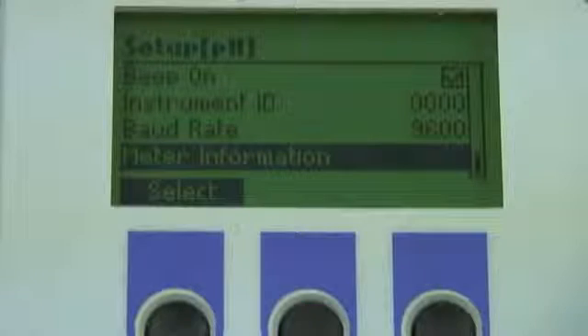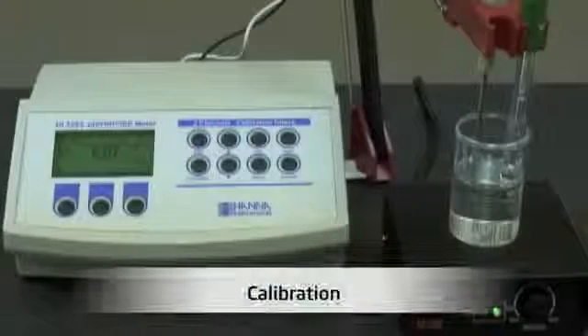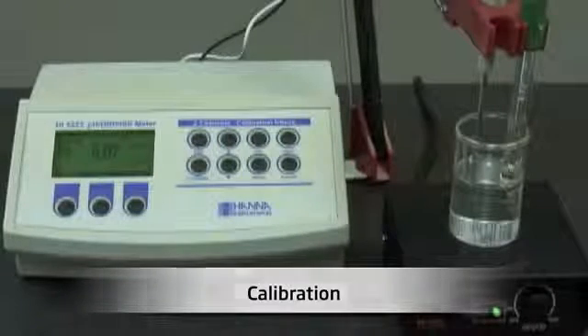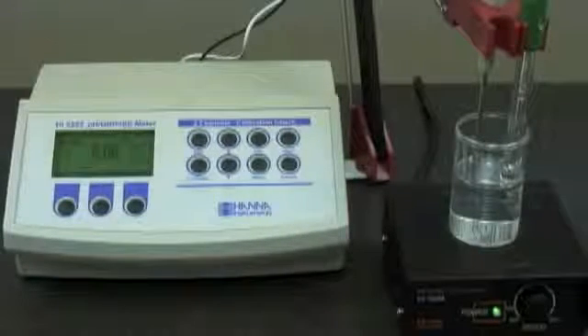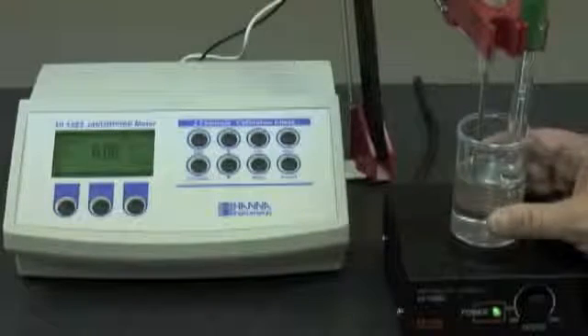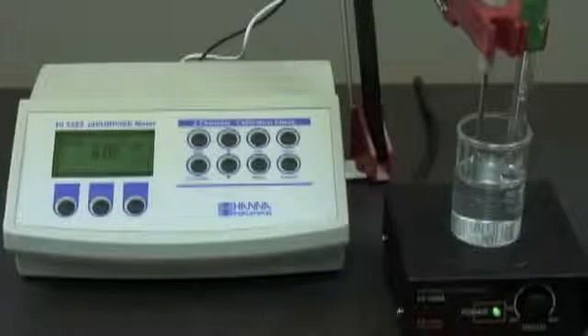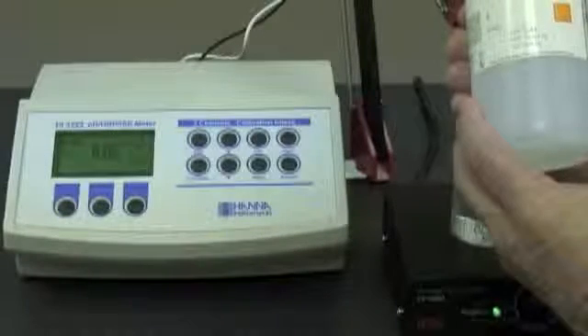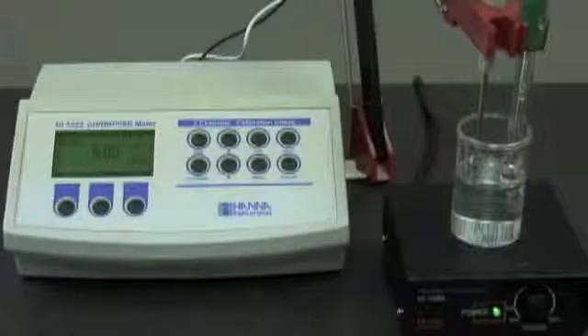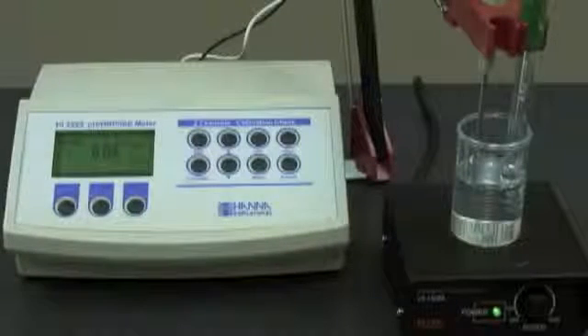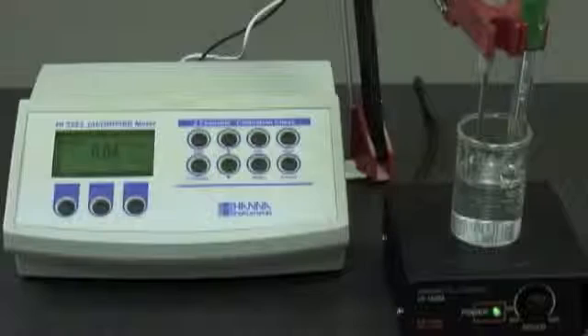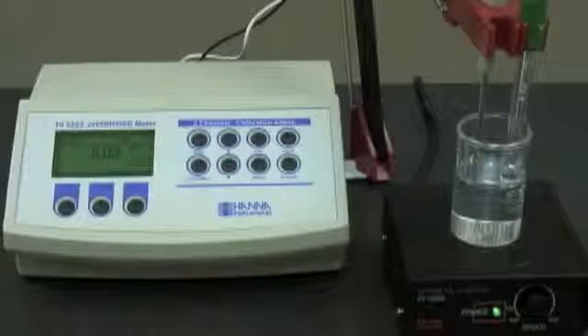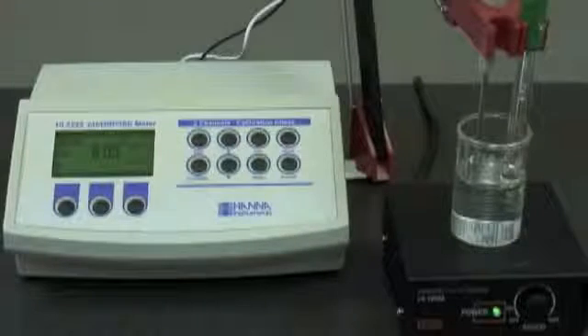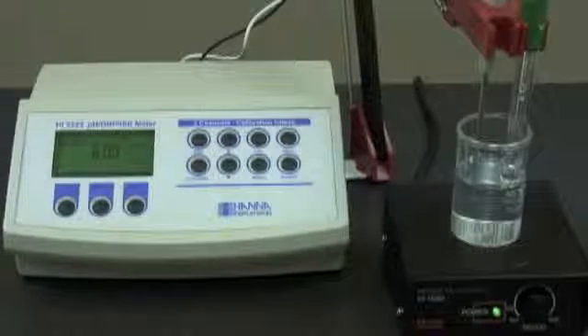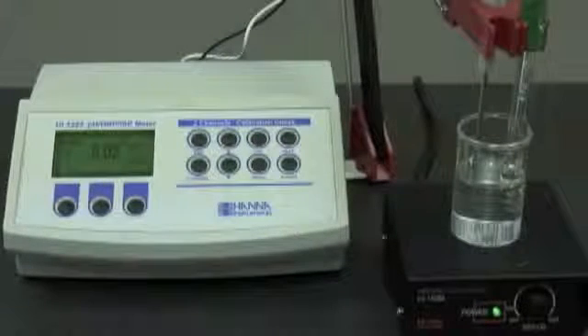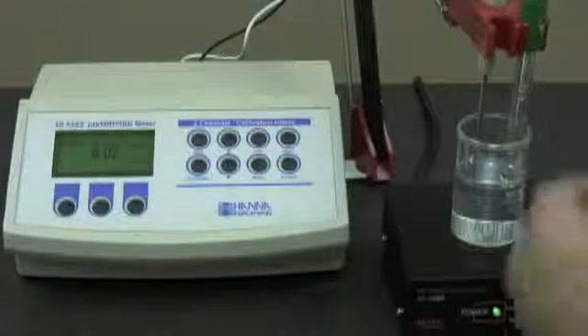Next, I'd like to show you how to calibrate it. Before we calibrate, it's very important to condition our probe first, especially if it's new. What I've done here is I've taken the liberty of putting my probe into a storage solution. And in this case, it's HI, Hanna Instruments 70300. Now, if you don't have a storage solution, it's okay to use a buffer as well, preferably number 4 as your first choice, and if you don't have a number 4, then number 7. So what I'm going to do is I'm going to wait for approximately 2 hours until my probe is conditioned. And what I've done here is I've already taken the fill cap off for demonstration purposes.